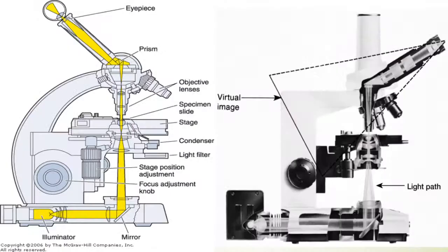But you also need to know this schematic diagram, which shows the path of light inside the microscope, and we have seen the presence of some prisms. A prism is present in the body of the microscope, and also in some condenser lenses. These are prismatic elements used to prevent aberration, chromatic aberration.